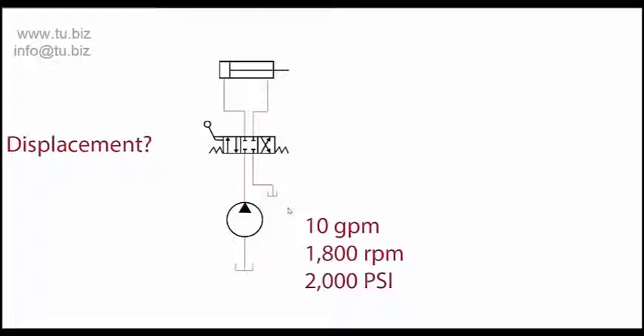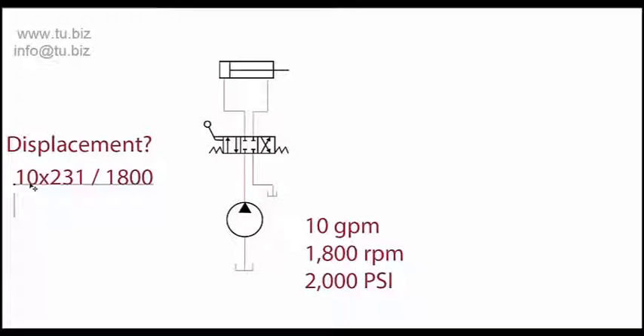So in this case we're going to have 10 GPM times 231, divided by the RPM. The RPM here is 1800, and that will give you the displacement.